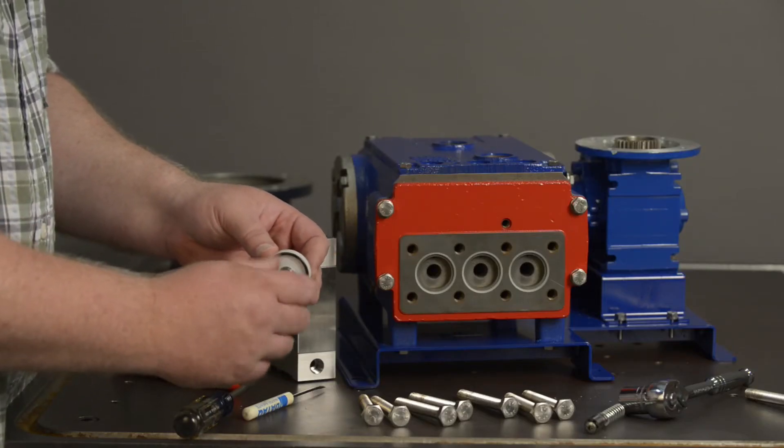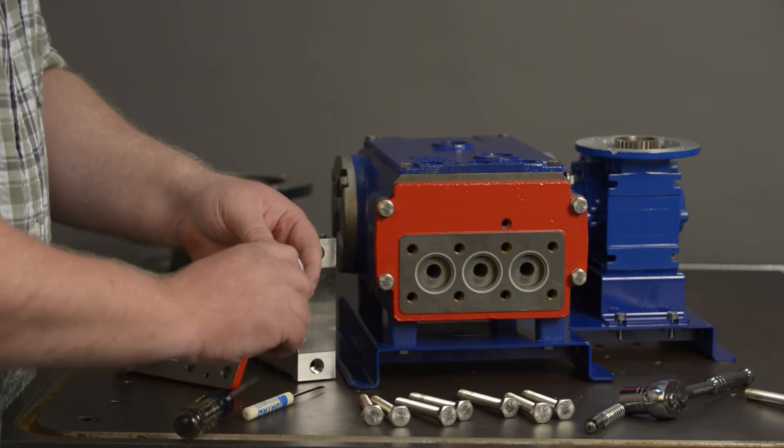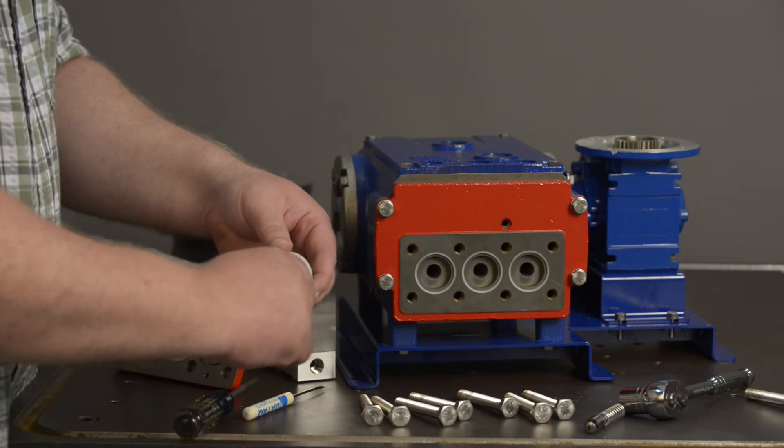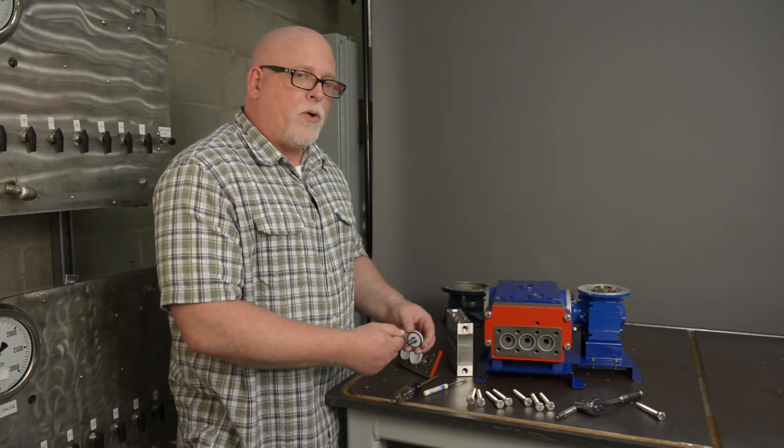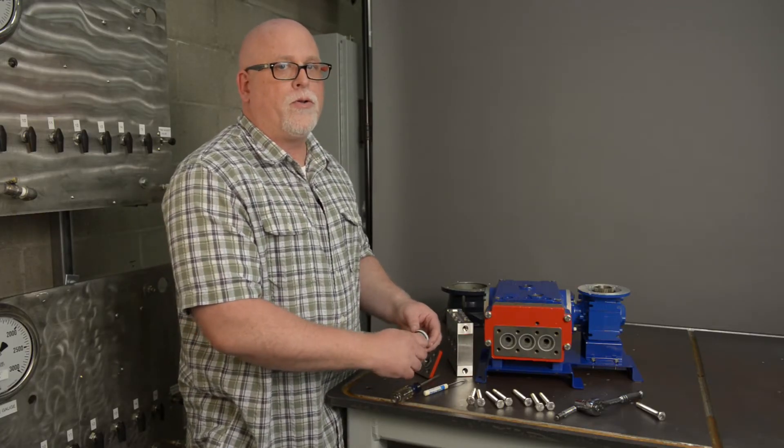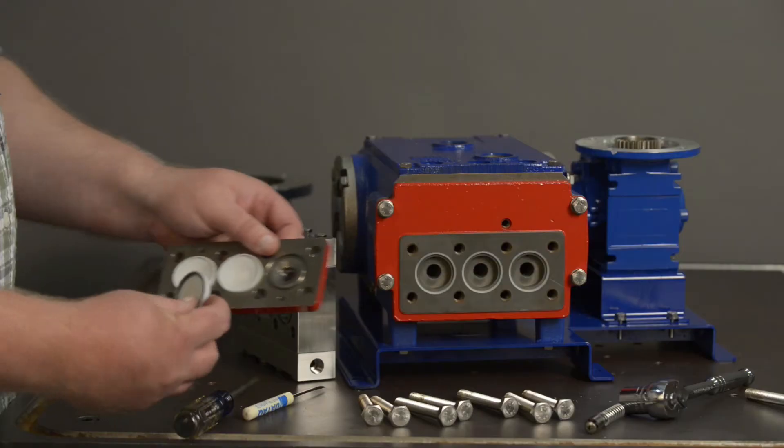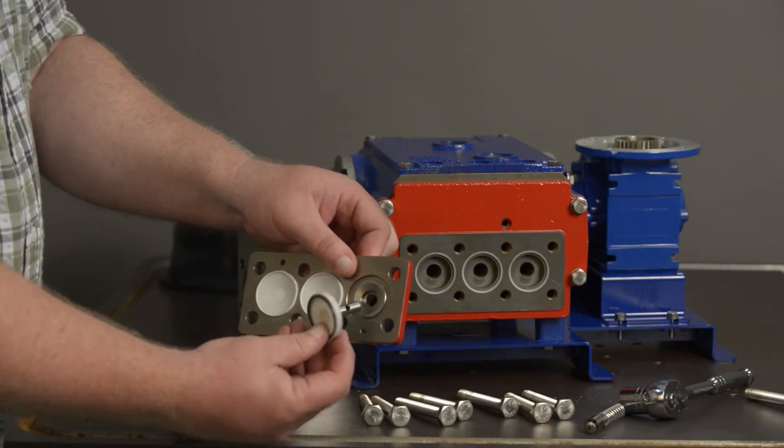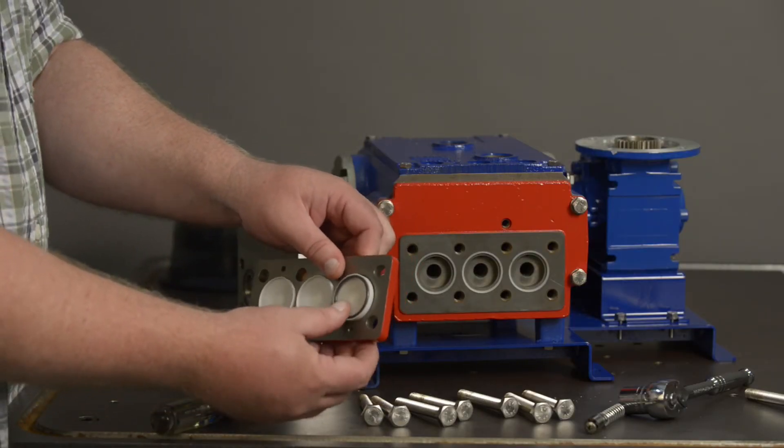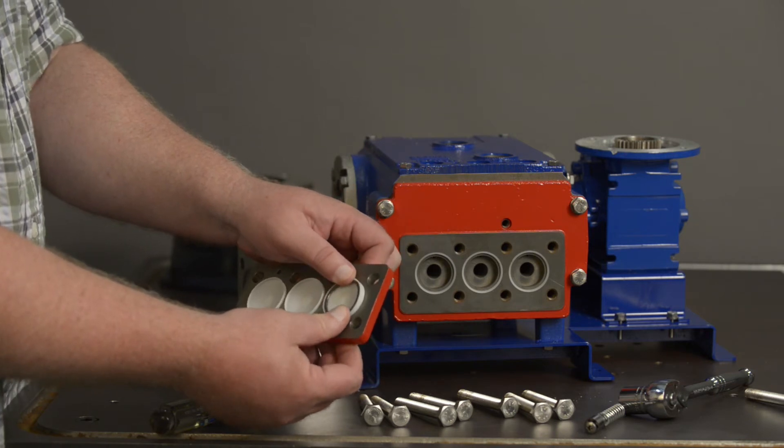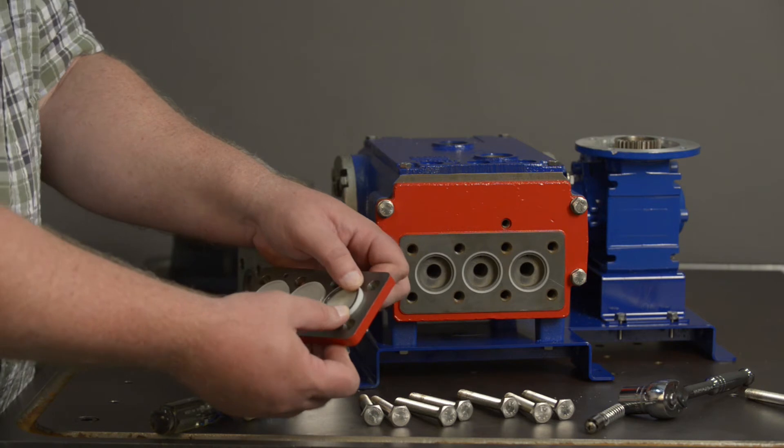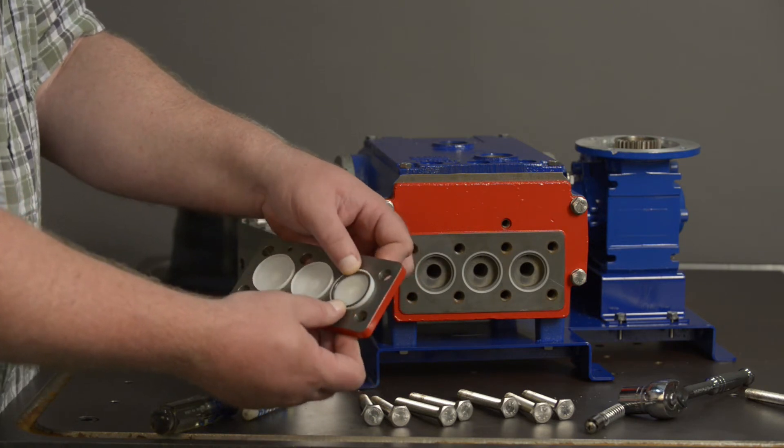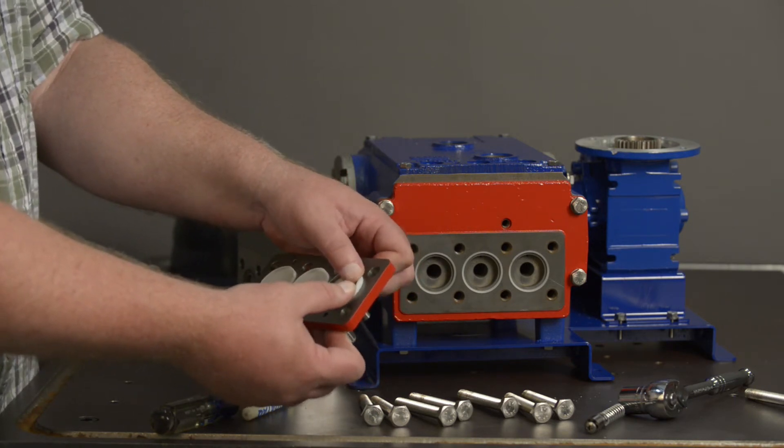You thread your post back onto the diaphragm and make sure that it's just finger tight, just so it's snug. It doesn't have to be over torqued or under torqued. Make it snug. Assemble the diaphragm through the diaphragm plate and make sure that it's nice and seated in there. You'll feel it. Run it around with your thumbs so everything is seated down inside of the diaphragm groove.